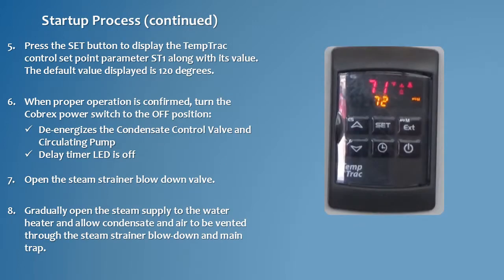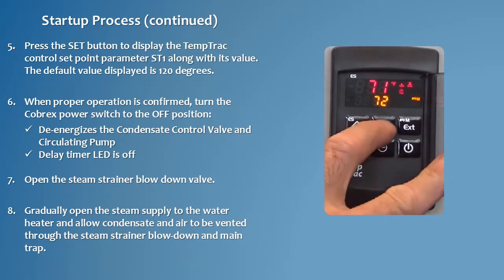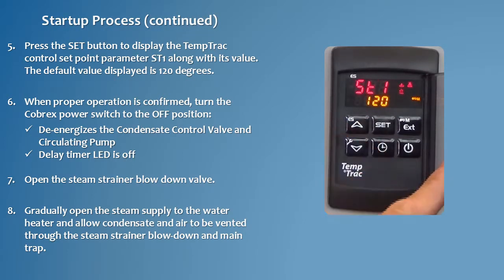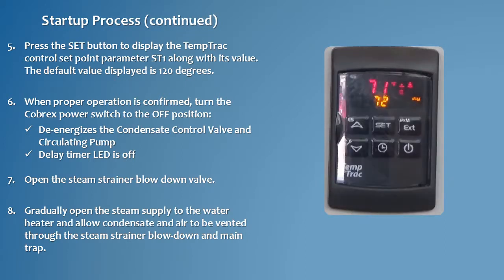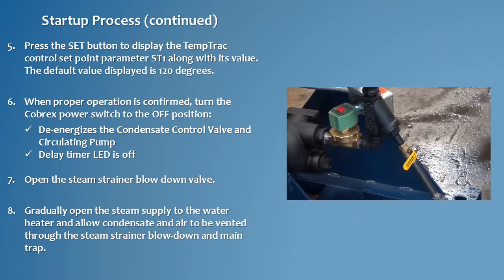Now check the TempTrac control set point parameter ST1. Press the Set button to display parameter ST1 along with its value. The value displayed is 120 degrees. When proper operation is confirmed, turn the power switch to the off position to de-energize the circulating pump and condensate control valve. Open the steam strainer blowdown valve.